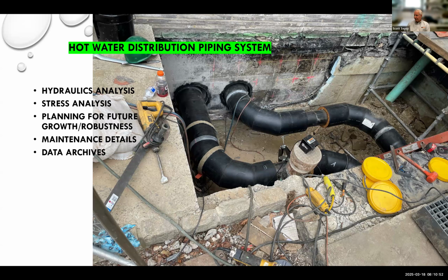We're also careful about flushing piping and chemical passivation of the new piping system, and monitoring water chemistry to avoid corrosion. And this piping system has built-in leak detection too, where we can pinpoint a leak. I understand that Brown University has reused some steam distribution piping for hot water, and we've done this inside of buildings where it makes sense.